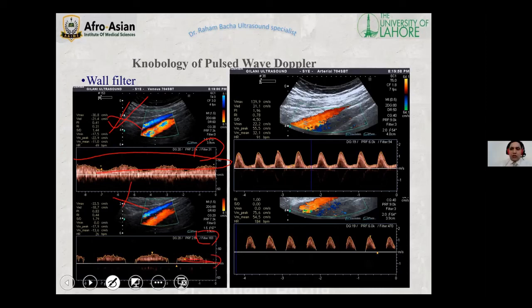That area now appears black, and only the top of the spectra appears, and the rest of all the Doppler shift which is near to the baseline was eradicated. In the same way, in the second example, the first example was a venous examination. This was venous, okay, and the second is an arterial examination. This is artery pulsatile flow. So you can see here in this image, the wall filter is 94, and the flow near the baseline is also present in this image.